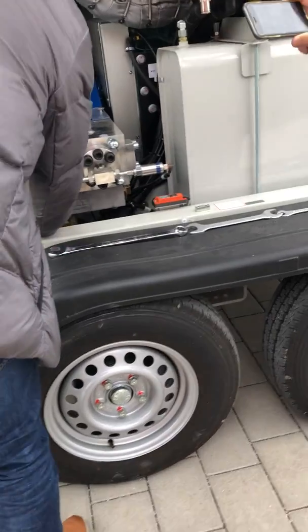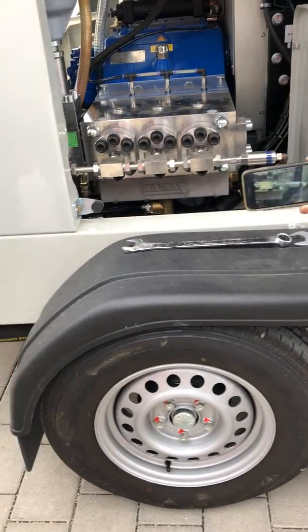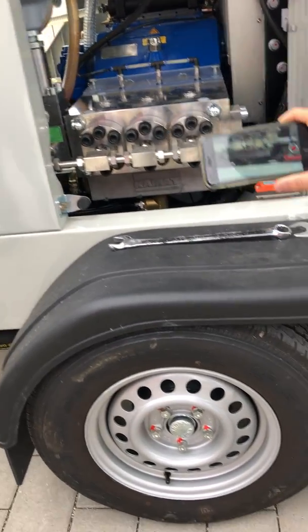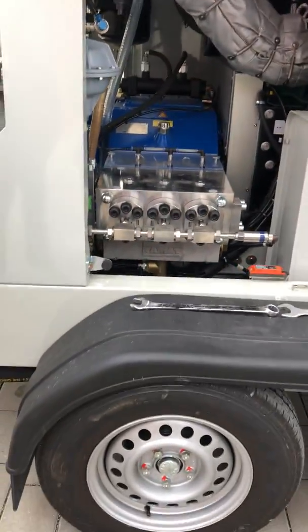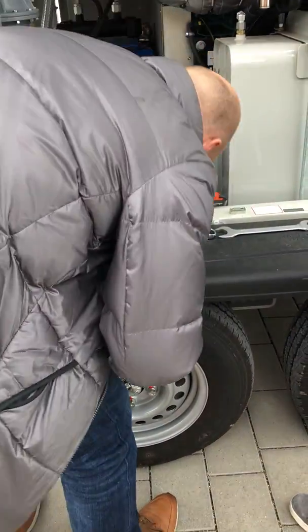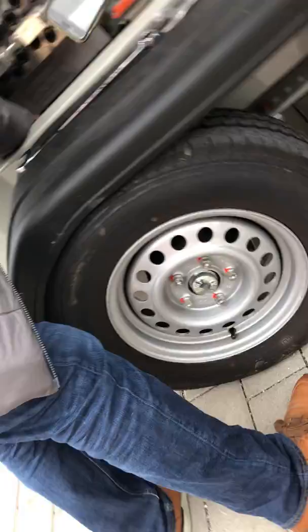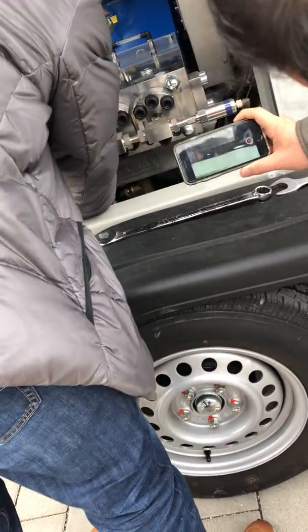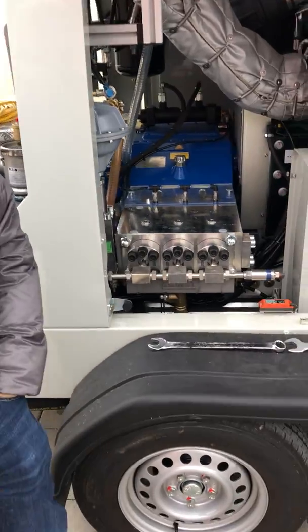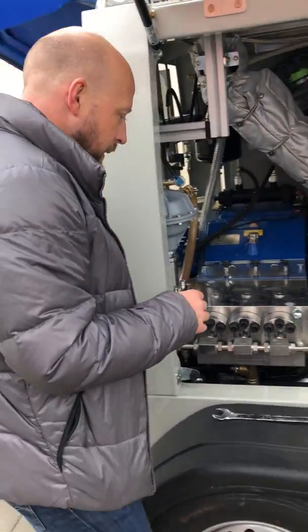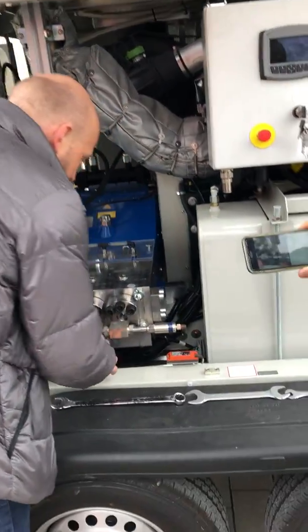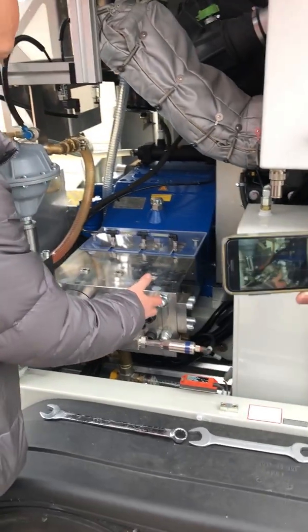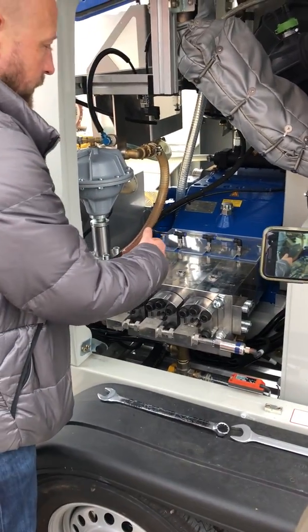So here we go in and we have a sensor, a low pressure sensor that should be sitting somewhere here. So that's the little hose going to the manometer and also to a pressure switch that is set to around 3 bar. Then we go into the pump.